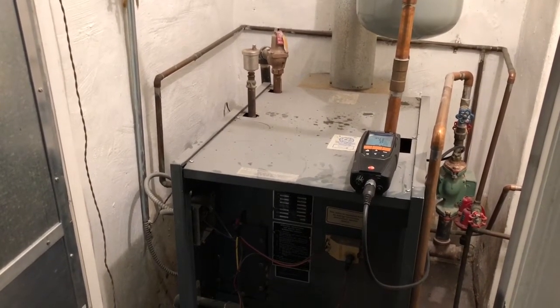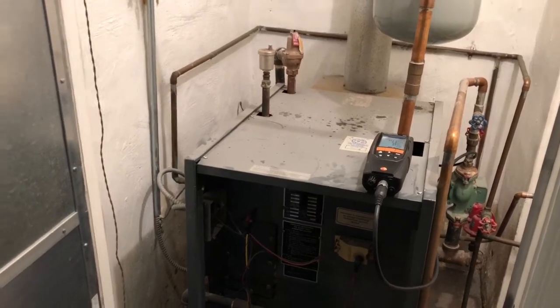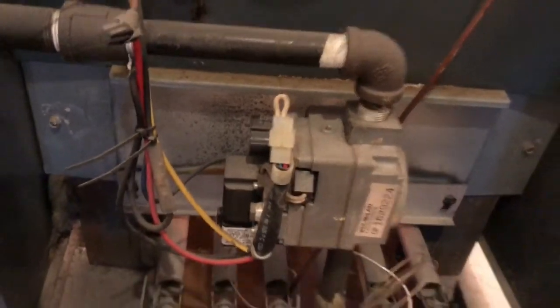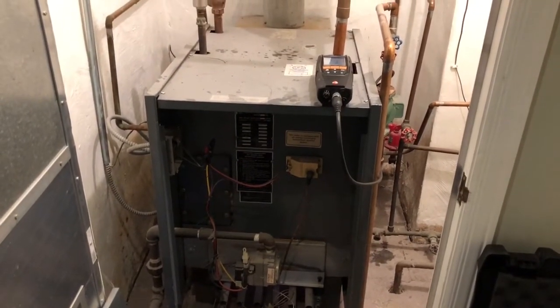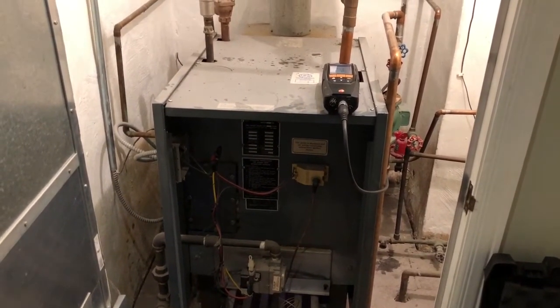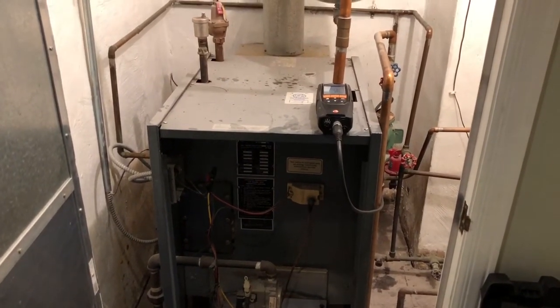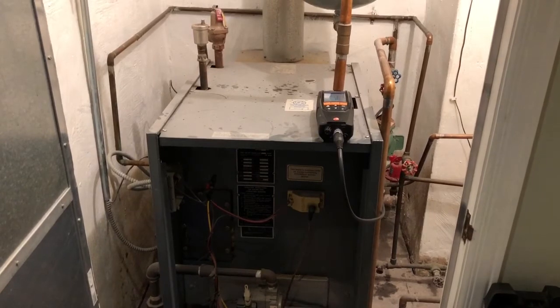Luckily, the boiler had some water. This boiler is from the mid-1980s — it has a White Rodgers flame rectification igniter and gas valve from that era. They didn't install low water cut-offs back then, so luckily for this homeowner, the system didn't cause any property damage or physical harm to anyone.